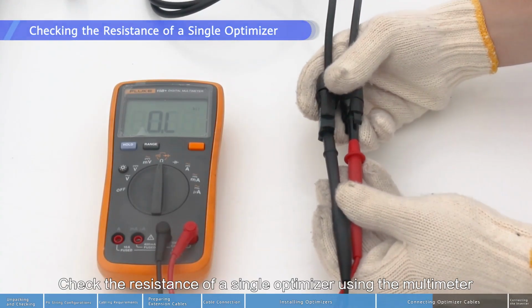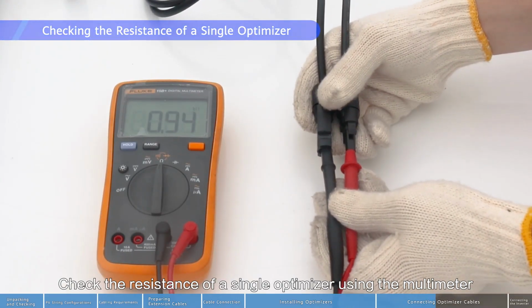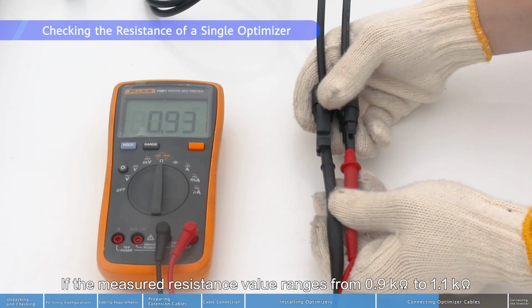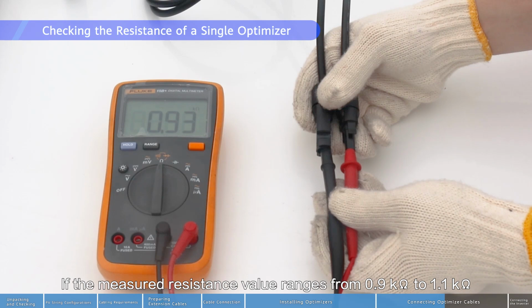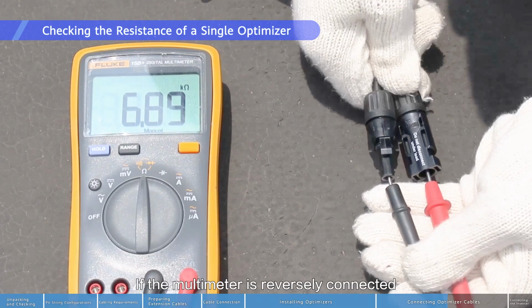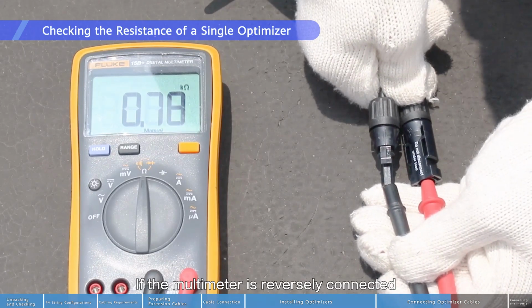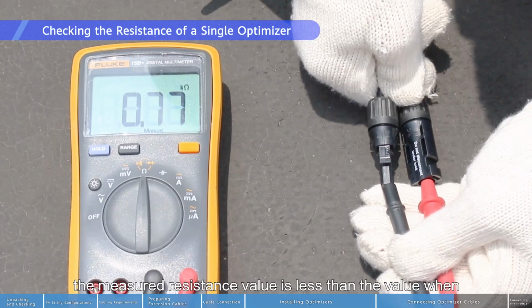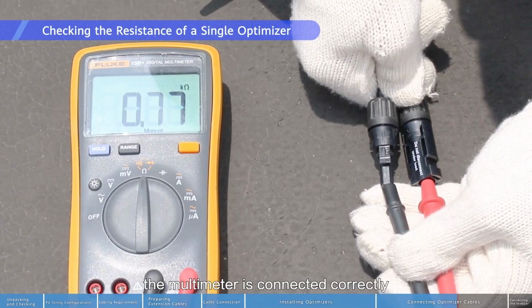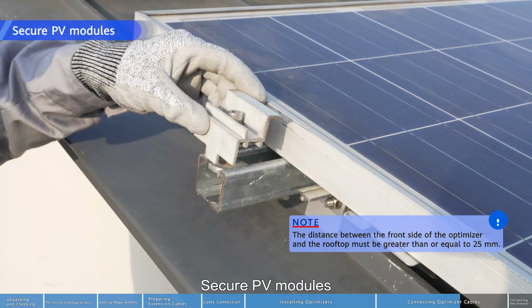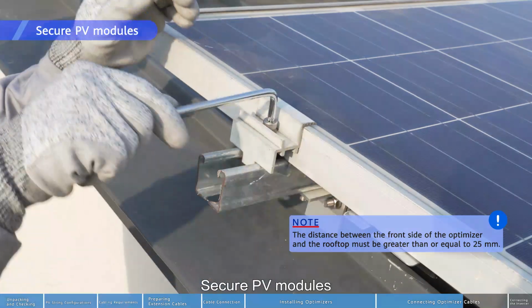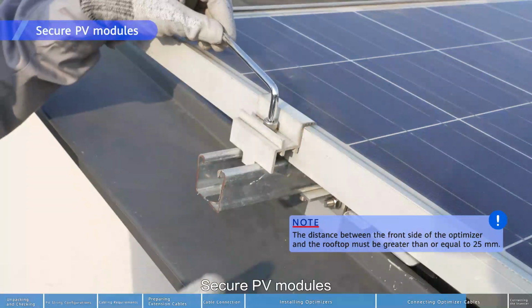Check the resistance of a single optimizer using the multimeter. If the measured resistance value ranges from 0.9 kiloohm to 1.1 kiloohms, the optimizer is normal. If the multimeter is reversely connected, the measured resistance value is less than the value when the multimeter is connected correctly. Secure PV modules.